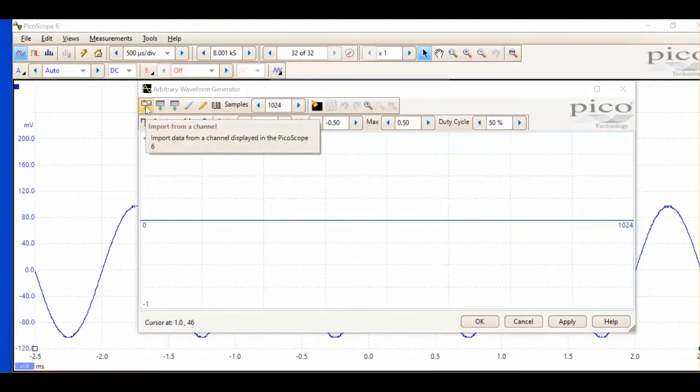we'll see the first one is import from a channel. Import data from a channel. This allows us to import a waveform from the oscilloscope into the generator. Import from the CSV. This allows us to take a saved waveform and import it back into the generator.